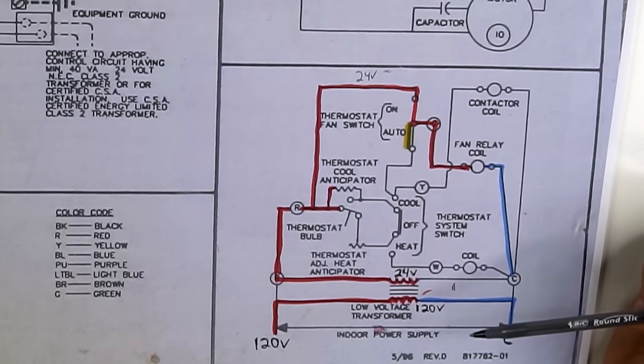From our disconnect box outside we have two hot legs coming into our air conditioner unit, both of them at 120 volts. This is a common question among new guys — where is the common? On a 240-volt AC unit, there is no common. You just have two hot legs that give you 240 volts. If one of the hot legs is missing, like if one disconnect fuse is blown and you're only getting 120 volts, nothing will turn on because the compressor and fan motor both need 240 volts to run.